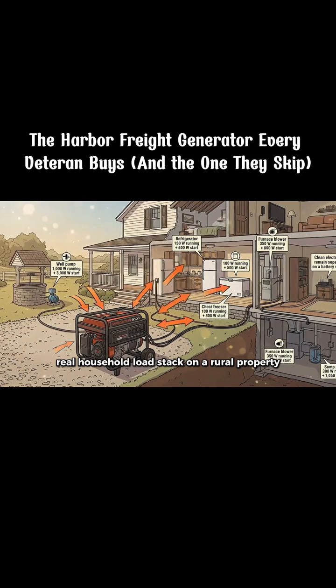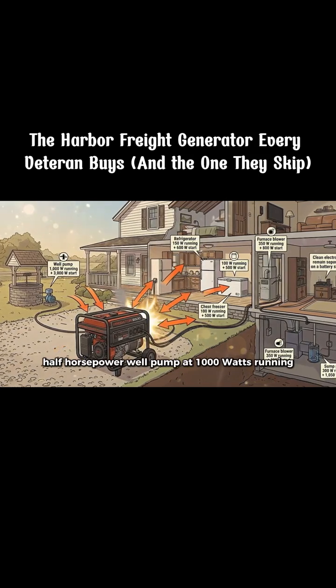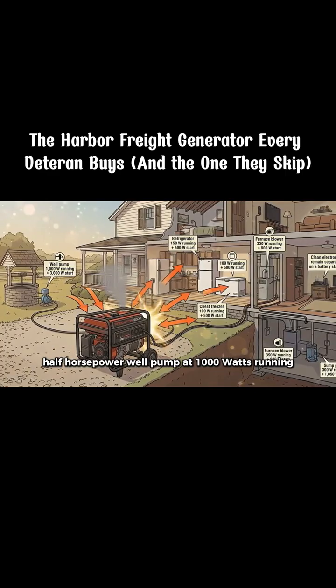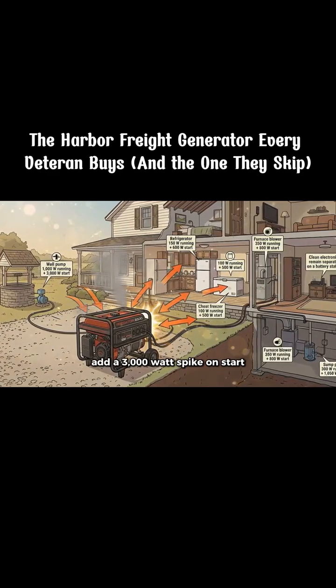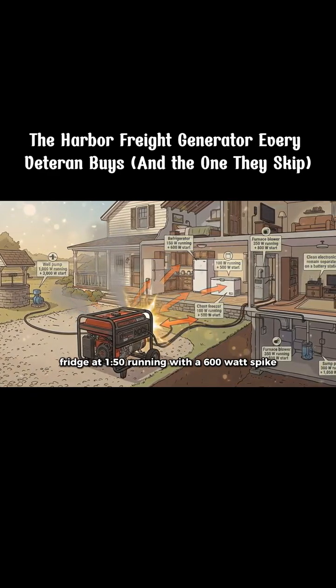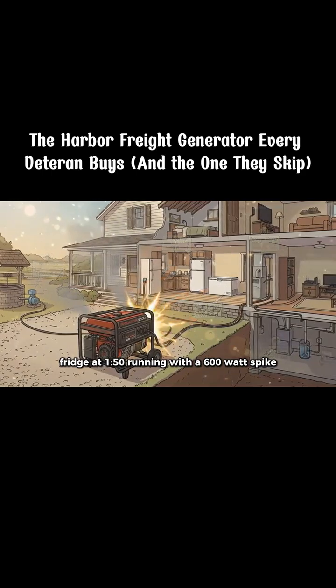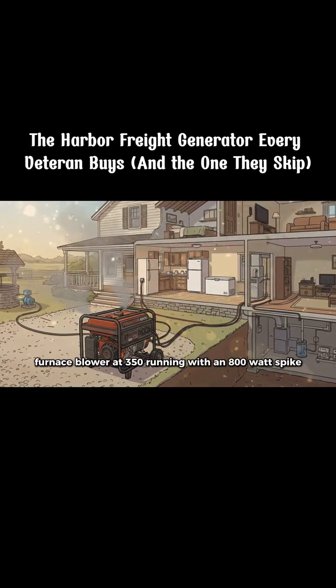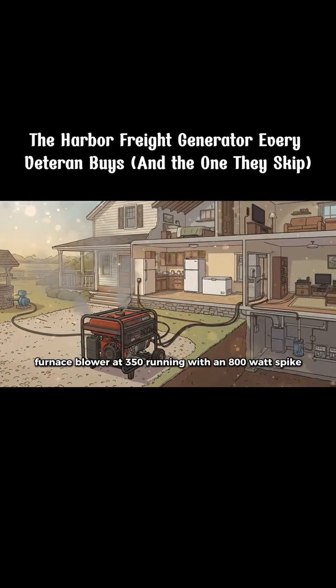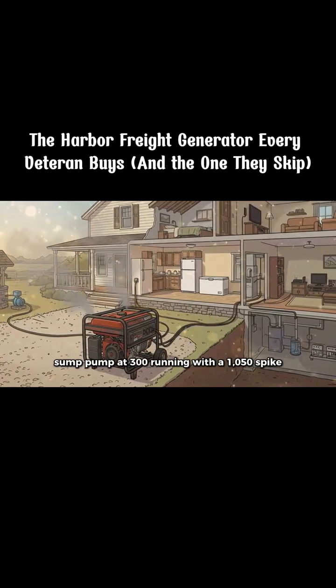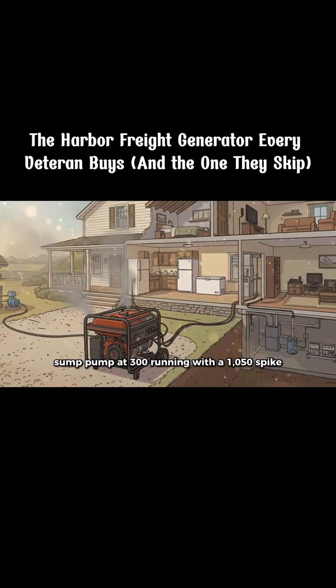Real household load stack on a rural property. Half-horsepower well pump at 1000 watts running. Add a 3000 watt spike on start. Fridge at 150 running with a 600 watt spike. Freezer similar. Furnace blower at 350 running with an 800 watt spike. Sump pump at 300 running with a 1050 spike.